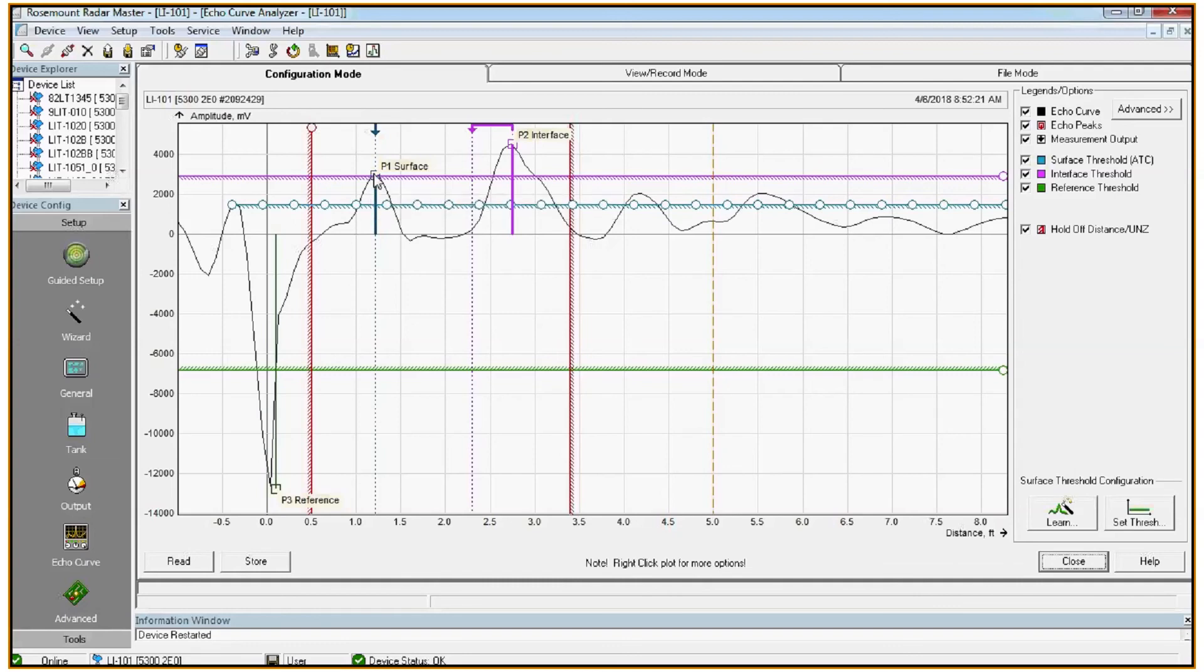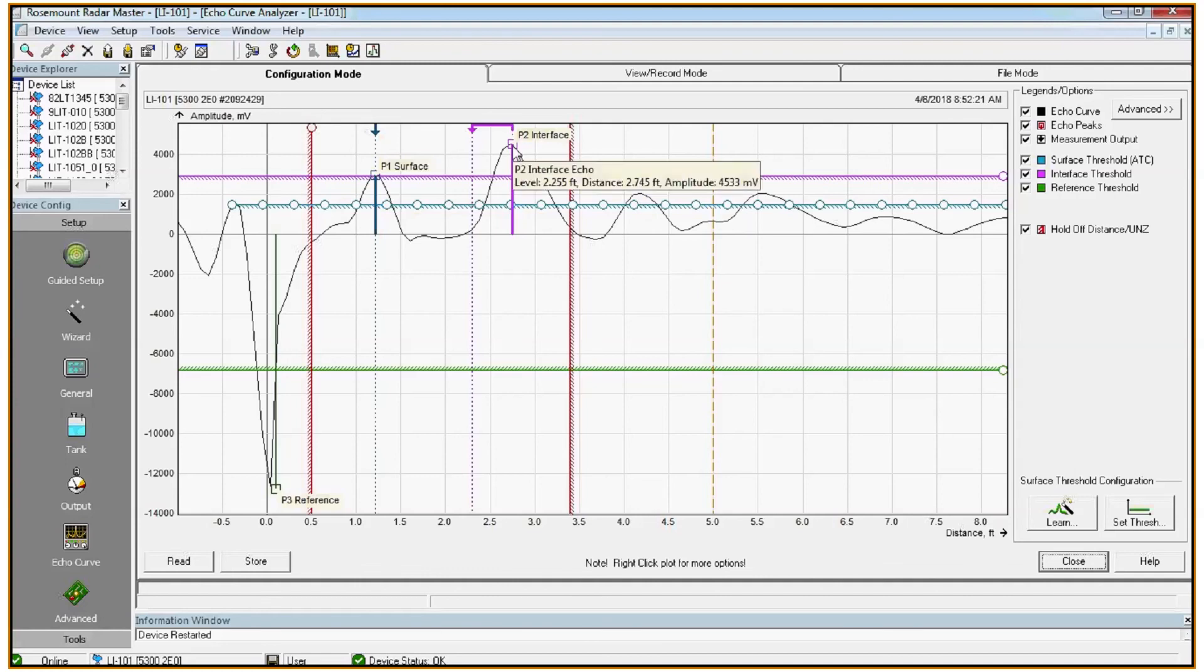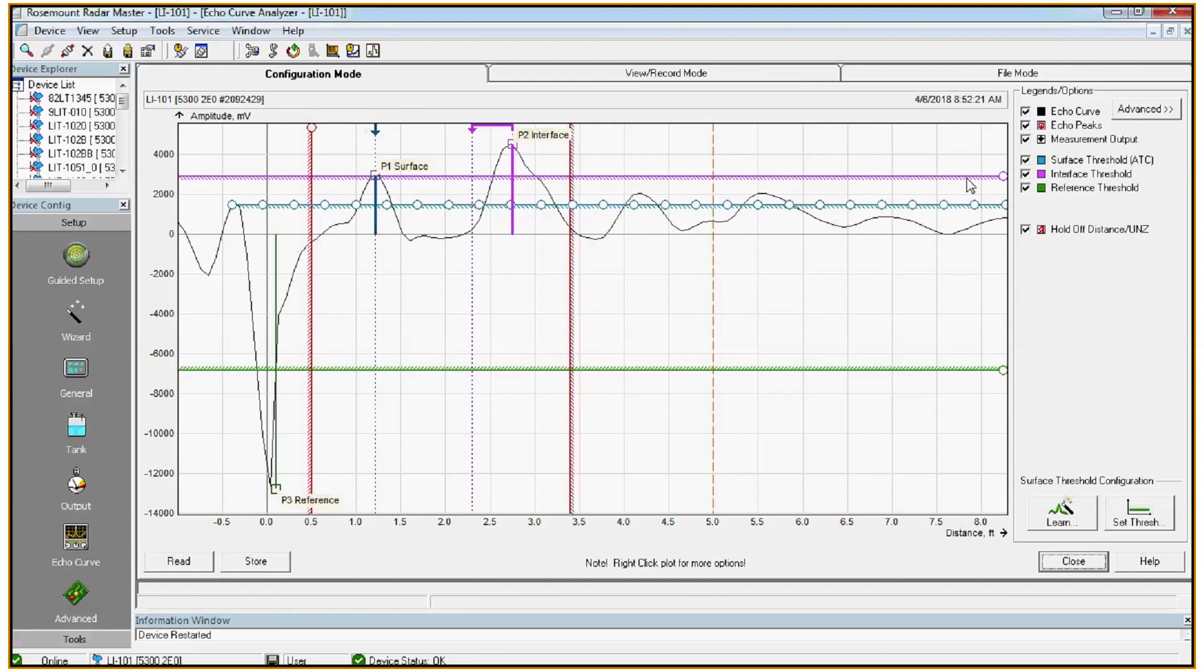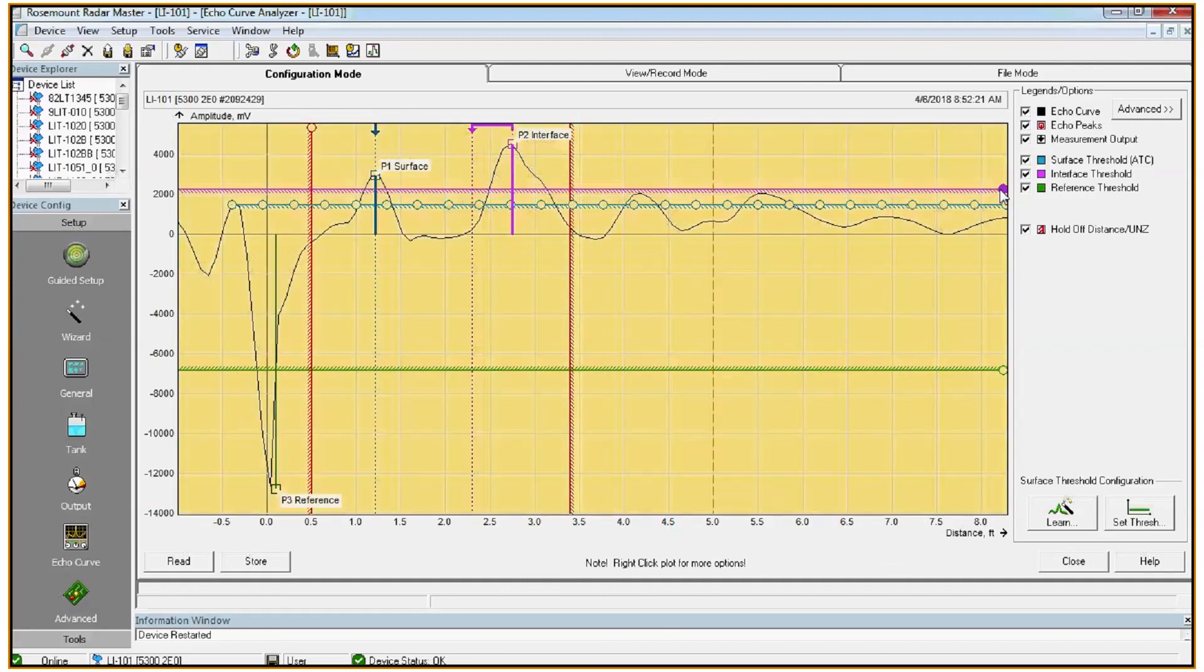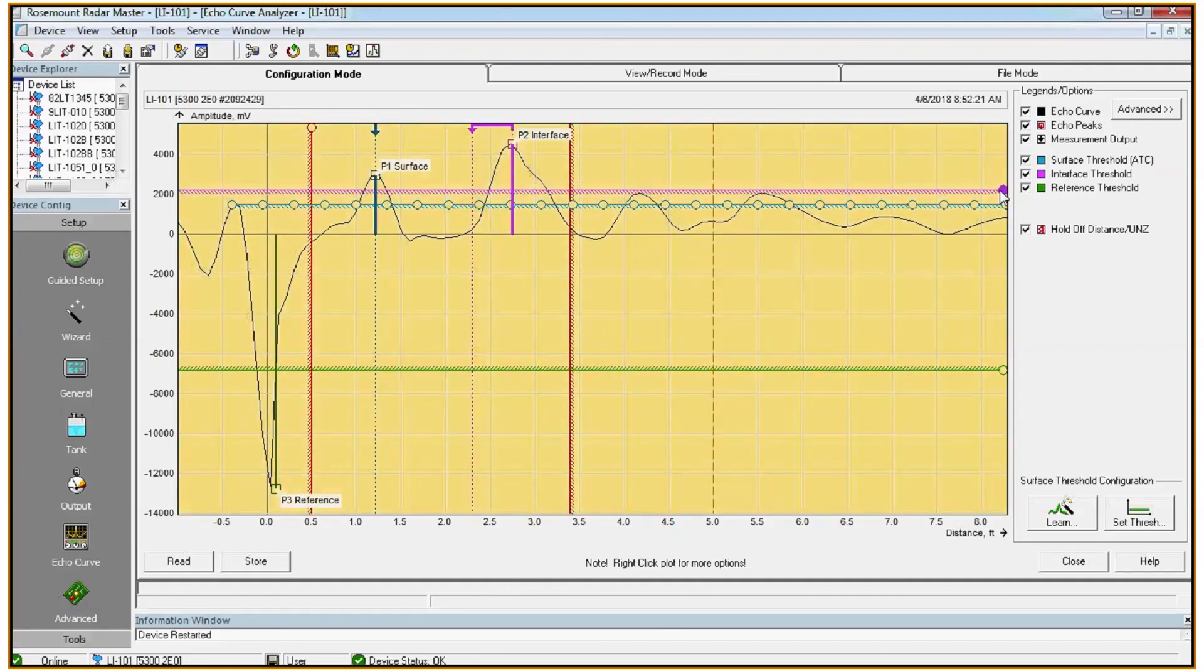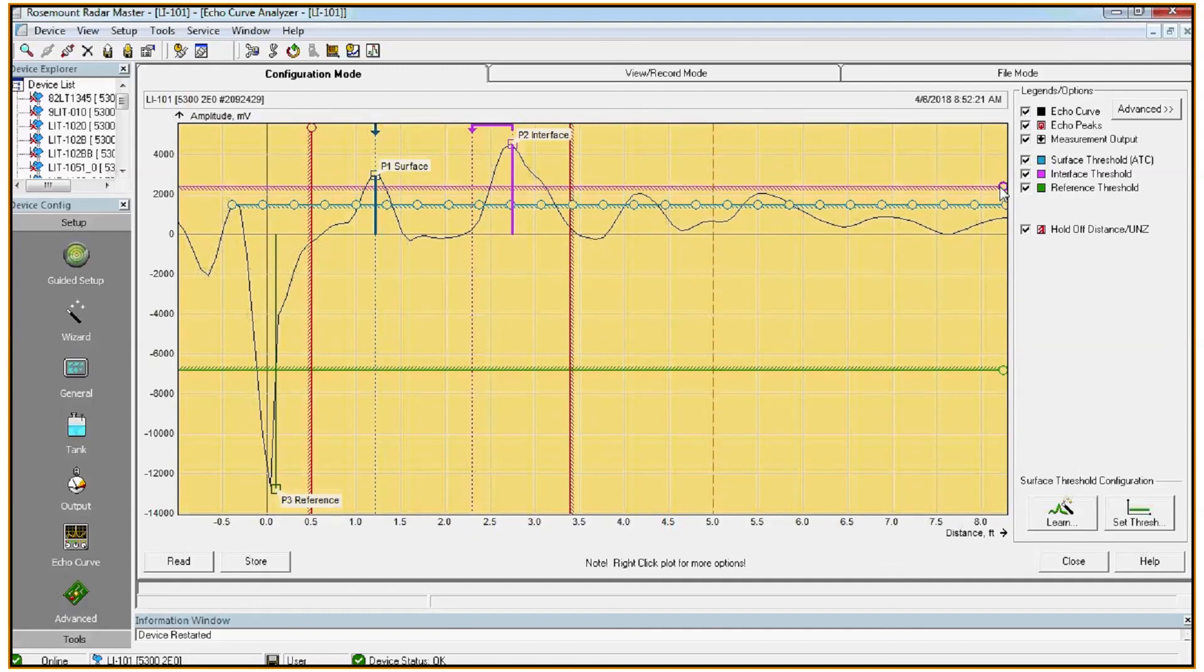The same rule of thumb applies for the interface threshold, which is the purple line. To identify an interface, we're looking for a peak after the surface peak that exceeds the purple line in amplitude. So here we see a peak further down the tank at about 4500 millivolts. So we would set the purple line to about half its amplitude. So we'll go for about 2100 millivolts. So we can just drag it down using this node on the right. When the area in the back of the plot is turned yellow, that means there's an unsaved change. So we want to click store to apply it.